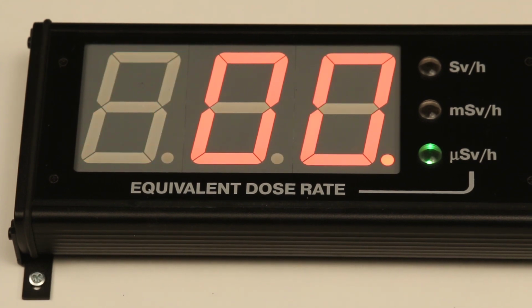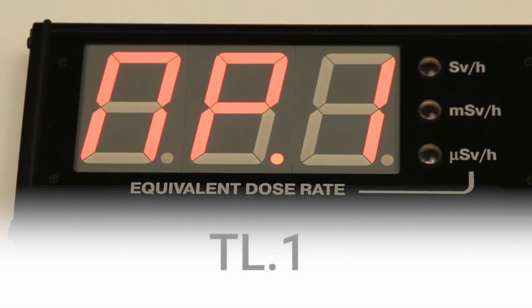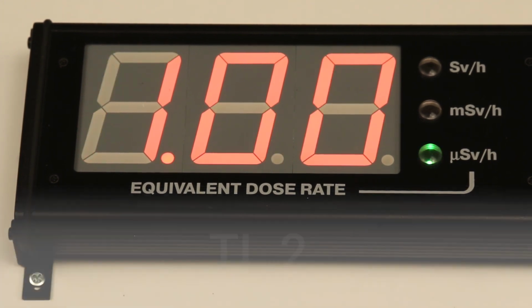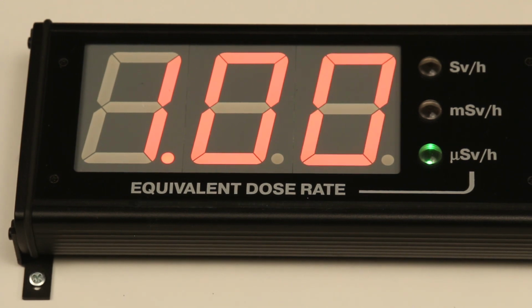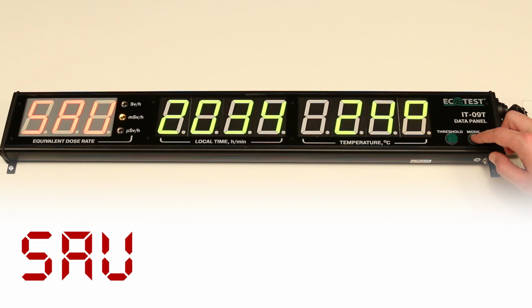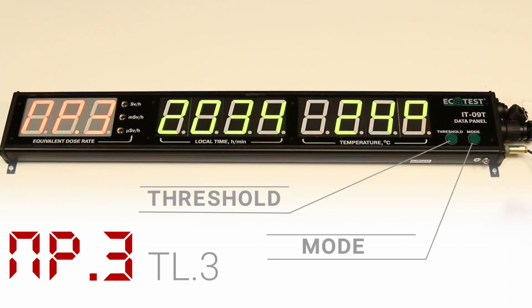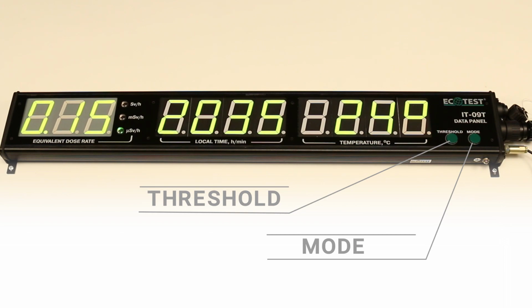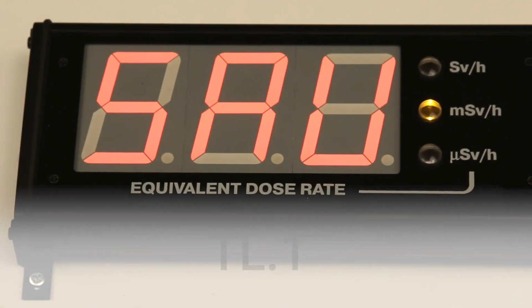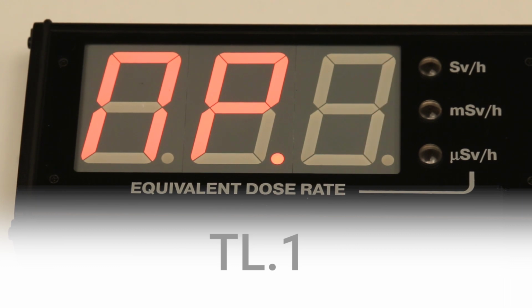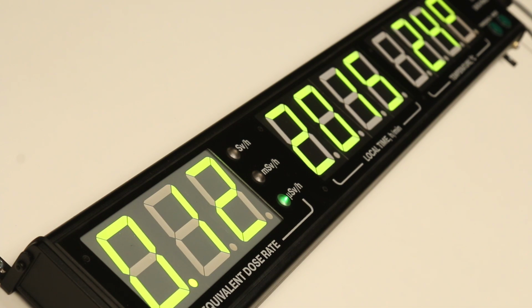After the value of the major figure is entered, the SAV symbol appears, and it shows that a new value of the threshold level is saved. Two red symbols and the threshold number show that the value of the threshold level may be changed. Changing of values for other threshold levels is done in the same way. To quit this mode, simultaneously press and release the threshold and mode buttons. If the buttons are not pressed within 80 seconds in the mode of the threshold level value change, the panel exits the mode and turns back to the mode of indication of gamma radiation dose rate, temperature, and real time.